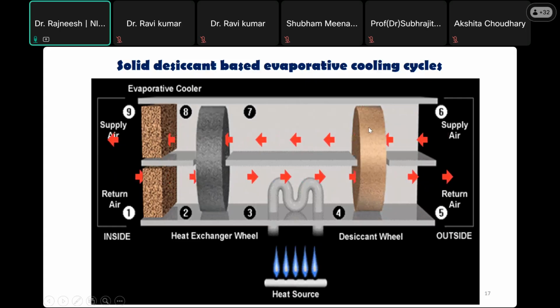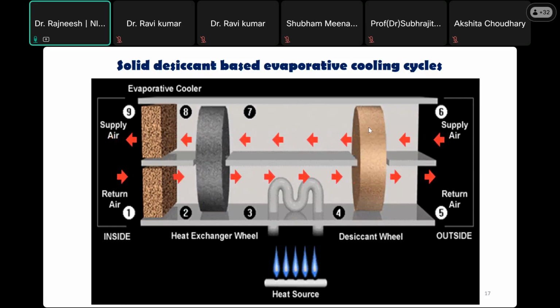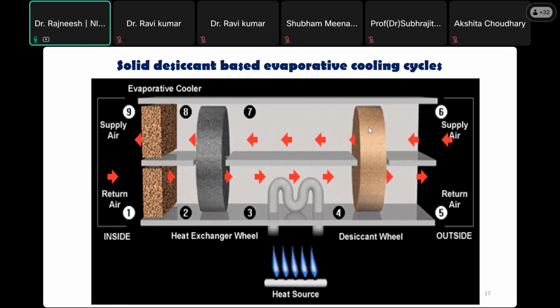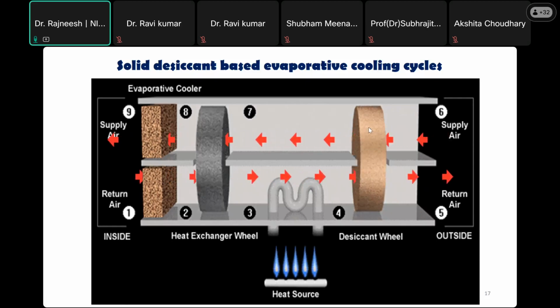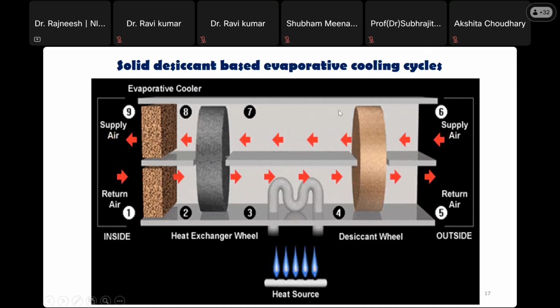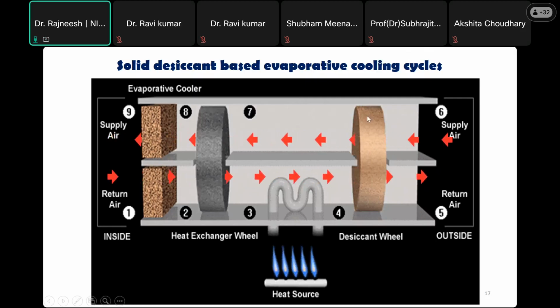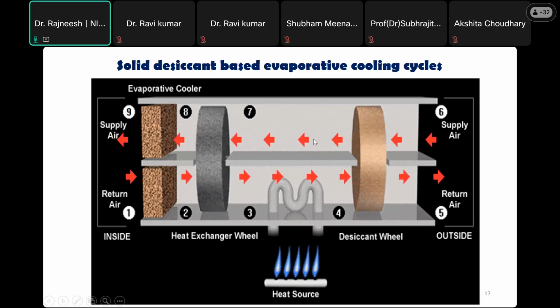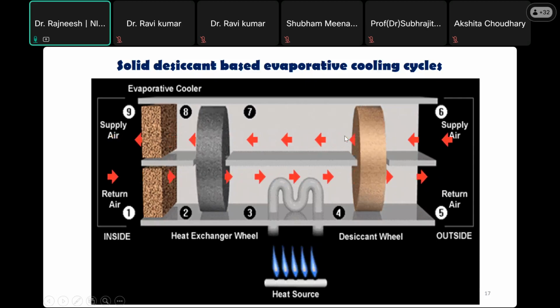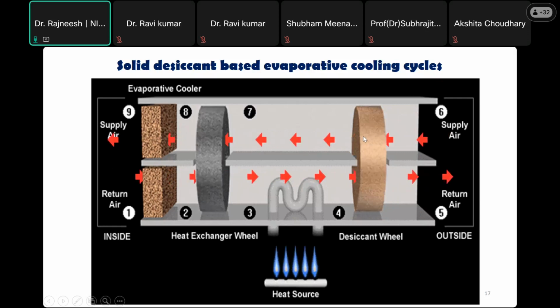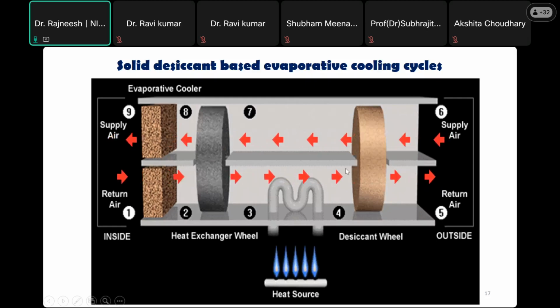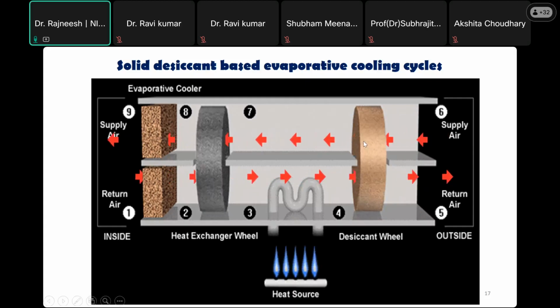In air conditioning, we basically have two types of loads: sensible load and latent load. Sensible load means we have the thermal load, heat. The temperature is required to be lower, and latent means we need to remove the moisture as well. So in the upper half, the moisture is absorbed from the atmospheric air. The air coming from the upper part of this desiccant wheel is now a little bit hot and dehumidified. Moisture is taken up by the material; we have the silica gel coating over the honeycomb structure within this wheel, which is known as the desiccant wheel. So the moisture is taken up by this wheel or the silica gel coating.